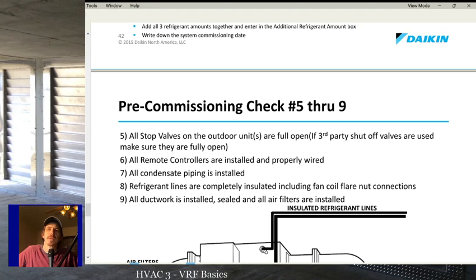We don't call them that because in cooling, if you're running the whole system in cooling, the discharge line doesn't need to be able to provide heat. And since that's the case, they use the line that is the discharge line and switch that over to a suction line. So going back to what I said, you have three lines, right? The three lines are really, these are what I want you to remember to call them, and this is something I'll definitely ask a question on.